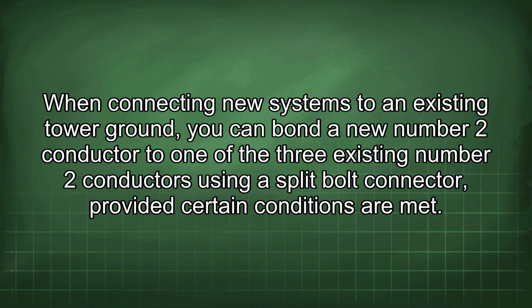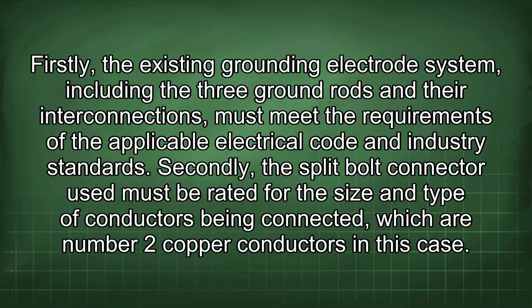When connecting new systems to an existing tower ground, you can bond a new number 2 conductor to one of the 3 existing number 2 conductors using a split bolt connector, provided certain conditions are met. Firstly, the existing grounding electrode system, including the 3 ground rods and their interconnections, must meet the requirements of the applicable electrical code and industry standards.